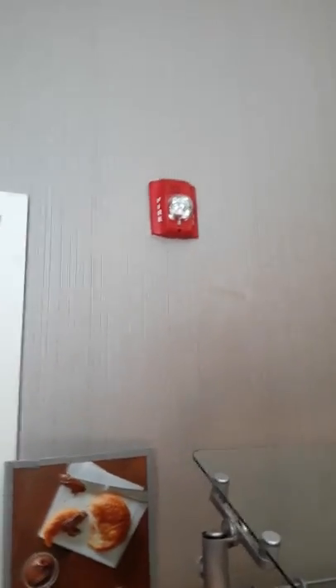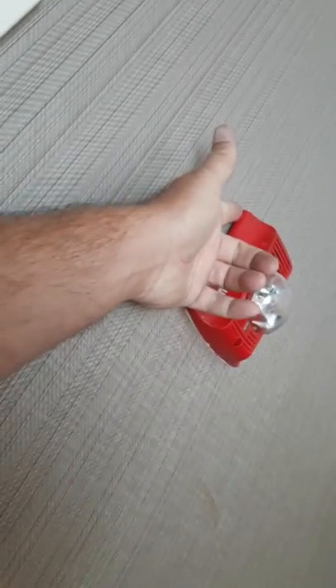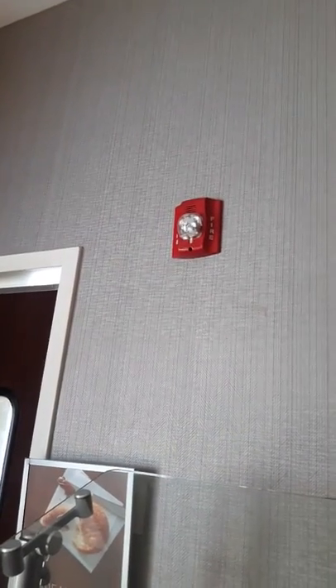They don't want to repair it right now, so I might have to leave it like that. The way I found it — I just walked up, grabbed a hold of it, and it popped free. The top corner was loose, so when I pulled it out it just popped all out. But that's the only thing I could find, and that's probably the intermittent trouble.